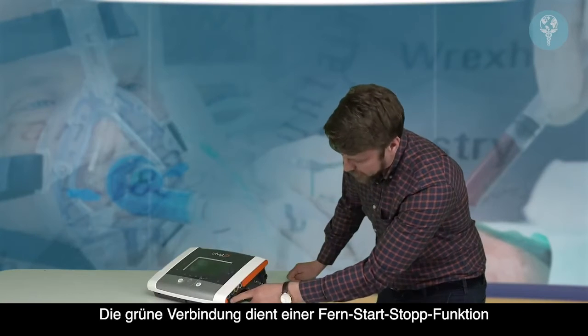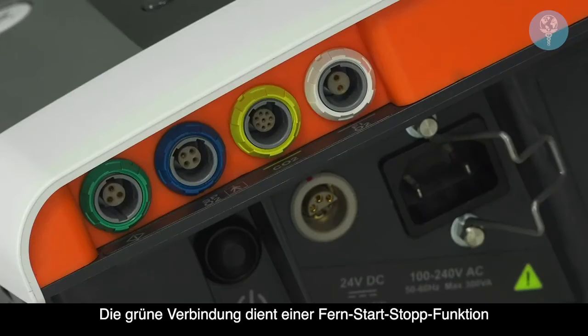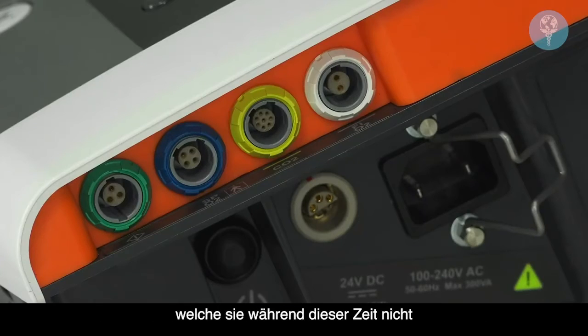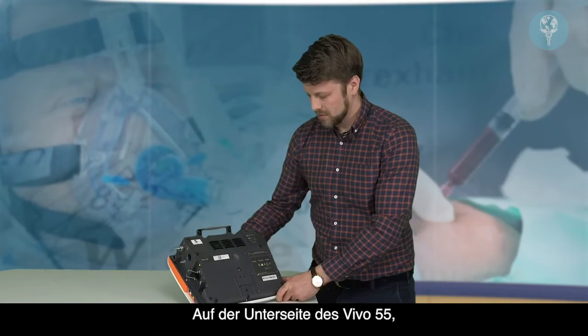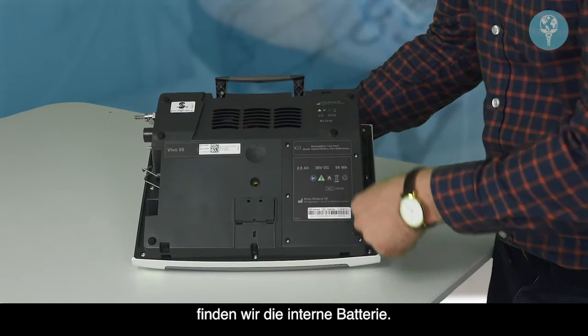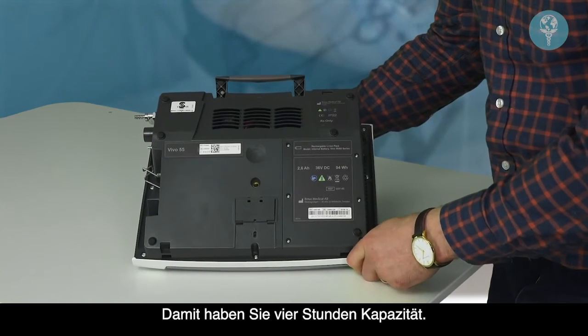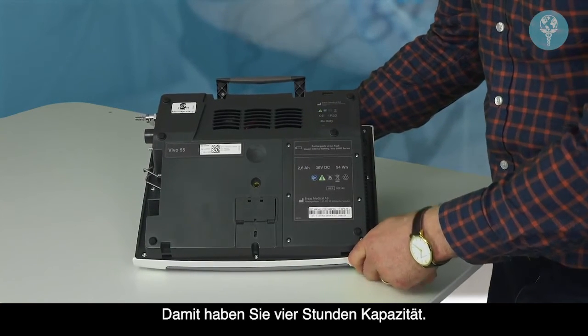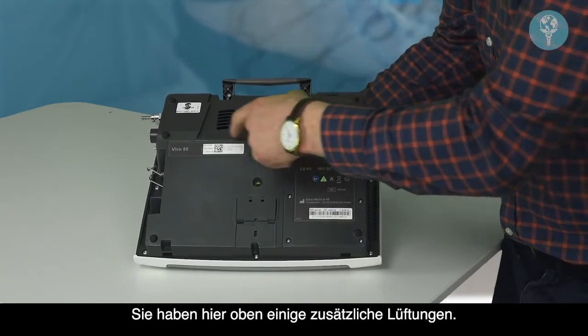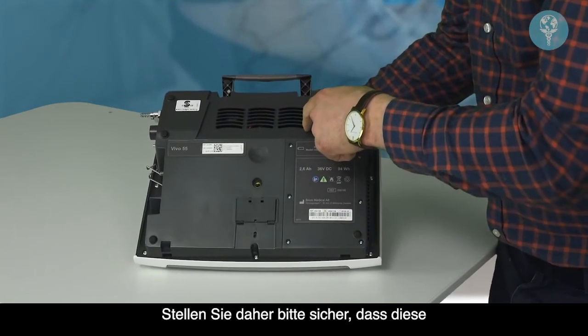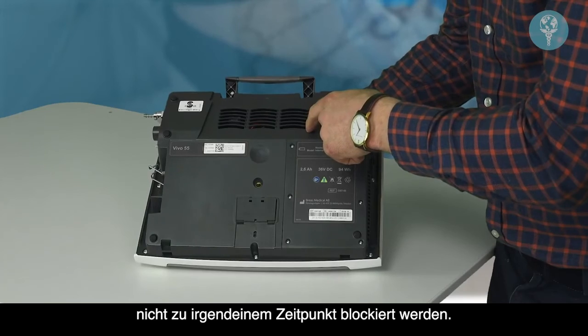The green connection is for a remote start-stop function, which during this time you would not be using in the hospital environment. On the underside of the Vivo 55, we can find situated the internal battery, which will give you 4 hours of backup. You also have some additional cooling fans on the top here, so please make sure these are not obstructed at any time.